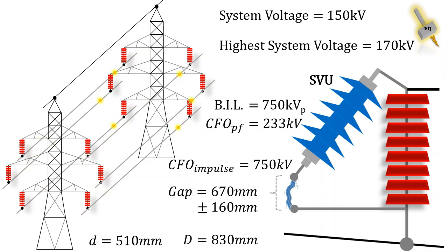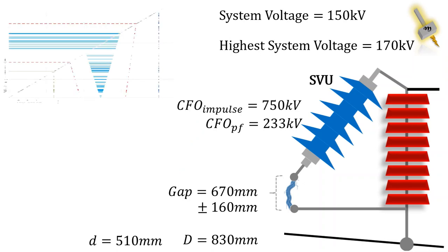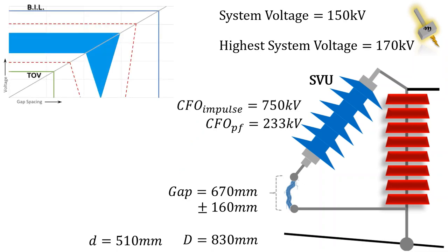Let's check what is the spark over voltage compared against the system BIL and system TOV. With 670 mm as the nominal value of spark gap, the lightning impulse spark over voltage is calculated as 396 kV peak. For this design, the spark gap has minimum 53% protection margin compared against the system BIL.